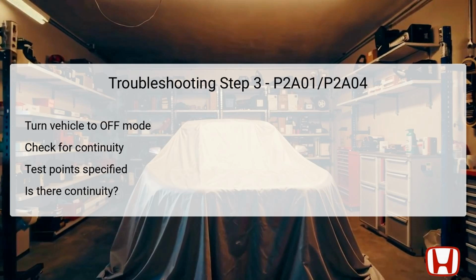If there is continuity, this indicates a definitive issue in the circuit that needs addressing. Conversely, if continuity is not established, it is not indicative of a fault with the wiring connected to the sensors themselves, prompting a shift to further diagnostics.